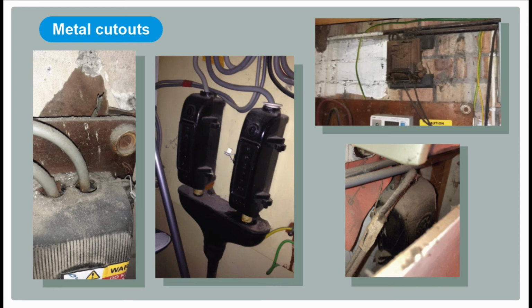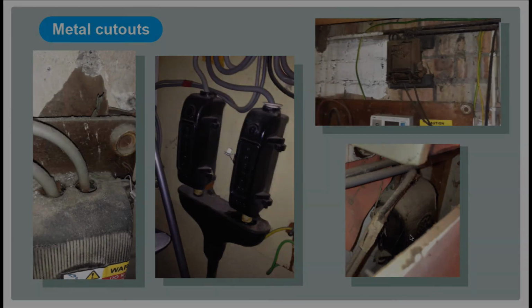As mentioned, the DNO are quite happy for metal cutouts to remain in continued service as long as they meet that set criteria. One of the points was that they'll replace the cutout if it's got a rewirable fuse in it. Now if you've got a really old cutout, it's bound to have a rewirable fuse in it, so it meets the DNO's requirements to replace it. So give them a call, send them a picture. If you're not sure, send them a picture, they'll have a look at it and tell you what they think.